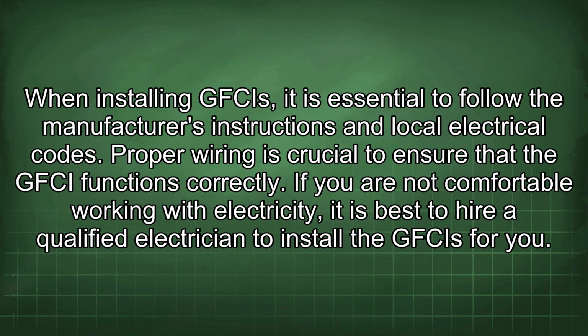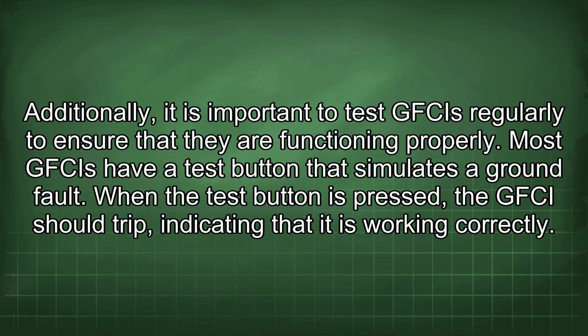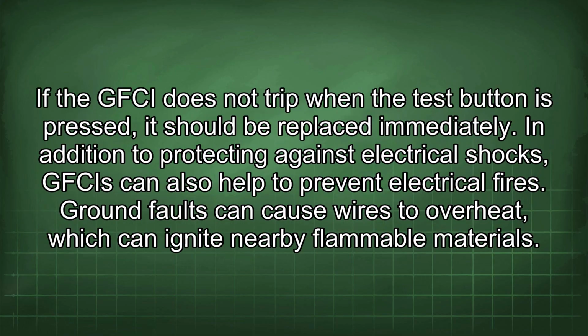When installing GFCIs, it is essential to follow the manufacturer's instructions and local electrical codes. Proper wiring is crucial to ensure that the GFCI functions correctly. If you are not comfortable working with electricity, it is best to hire a qualified electrician to install the GFCIs for you. Additionally, it is important to test GFCIs regularly to ensure that they are functioning properly. Most GFCIs have a test button that simulates a ground fault. When the test button is pressed, the GFCI should trip, indicating that it is working correctly. If the GFCI does not trip when the test button is pressed, it should be replaced immediately.